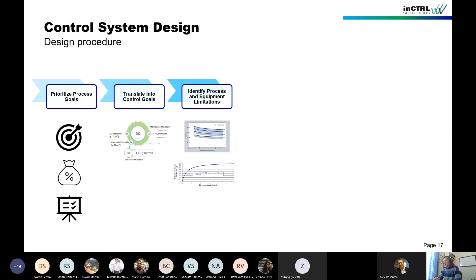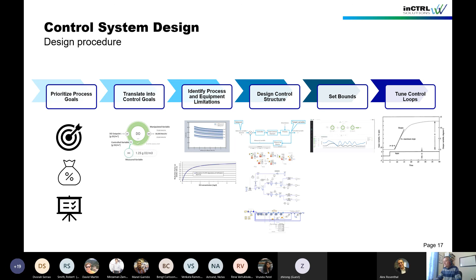One of the main design steps is to translate the process goals into control goals, right? And funny enough, you can actually achieve a process goal with a very, very bad controller performance, or vice versa, right? And the best solution, I would say, is if you can align process and control goals. I will walk through that in a sec. Then you should identify process and equipment limitations. I will give some examples as well for ammonia-based aeration control. And then you start putting together the control structure, knowing what you want to achieve and also knowing what the limitations are. Setting bounds is an essential step in that, and then in the end you tune the control loops. So that is a typical procedure we apply in our projects.